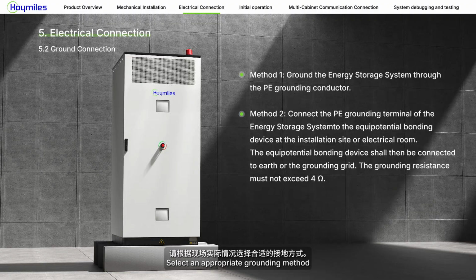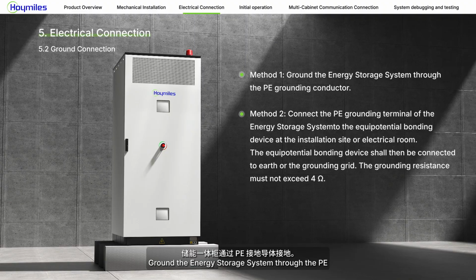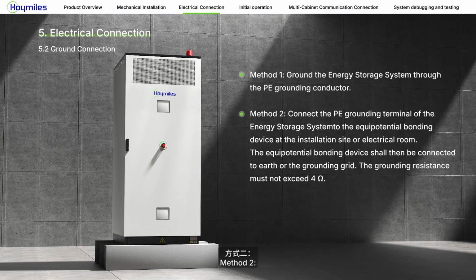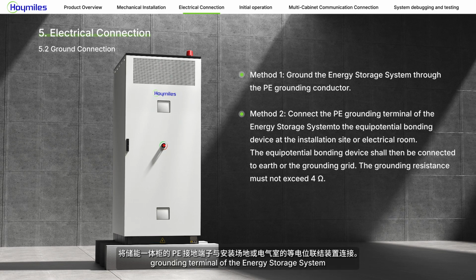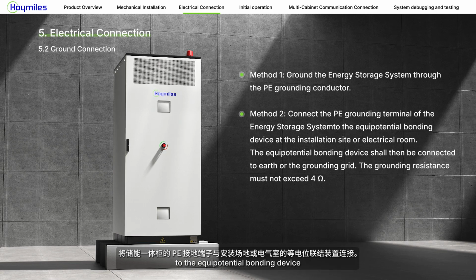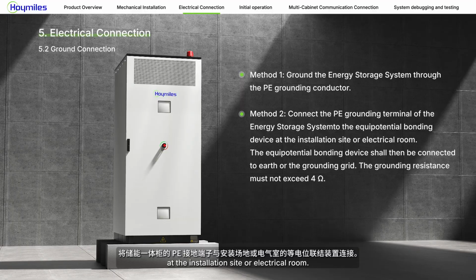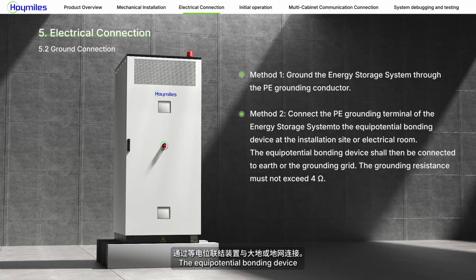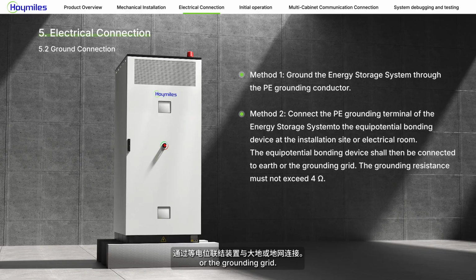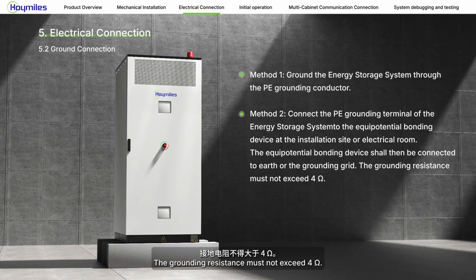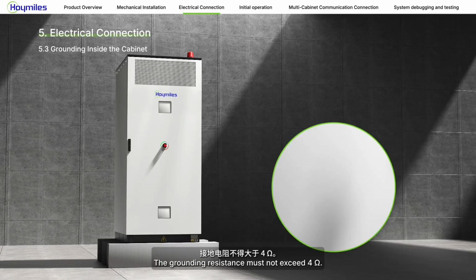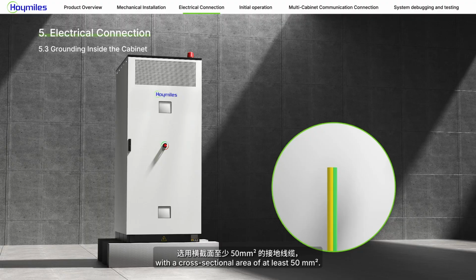Select an appropriate grounding method according to actual site conditions. Method 1. Ground the energy storage system through the PE grounding conductor. Method 2. Connect the PE grounding terminal of the energy storage system to the equipotential bonding device at the installation site or electrical room. The equipotential bonding device shall then be connected to earth, or the grounding grid. The grounding resistance must not exceed 4 ohms. Select a grounding cable with the cross-sectional area of at least 50 square millimeters.